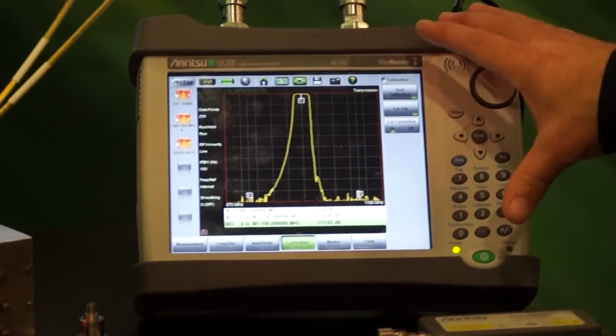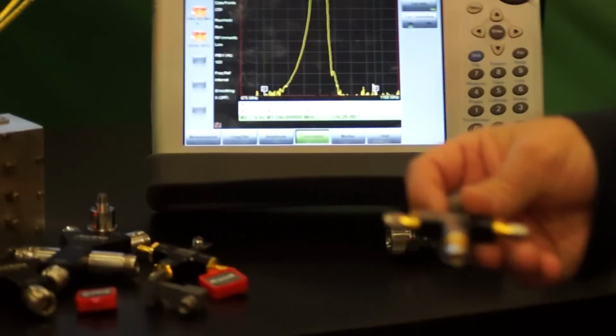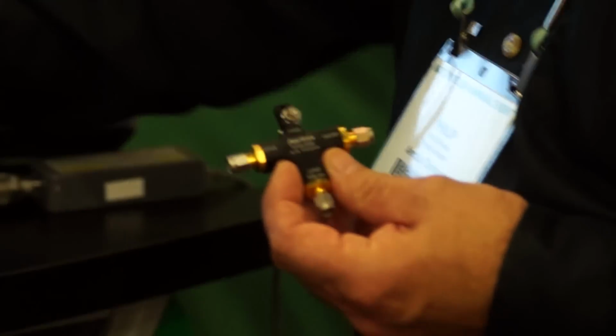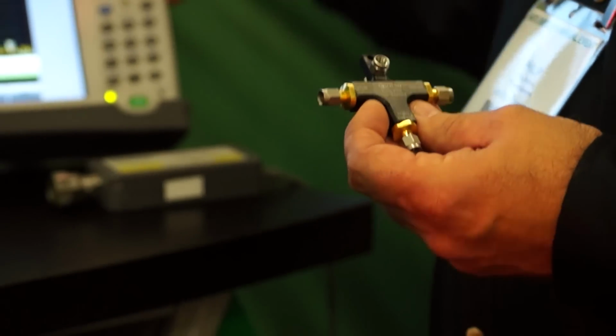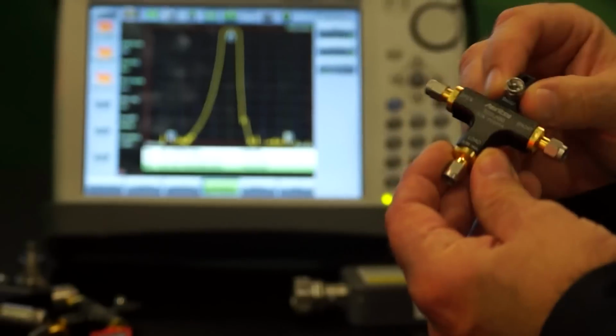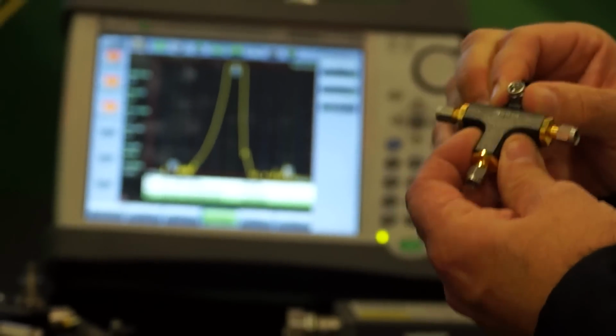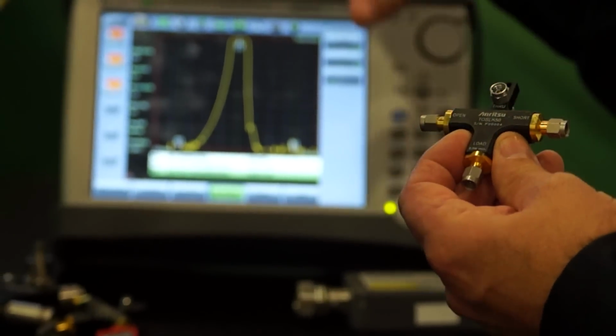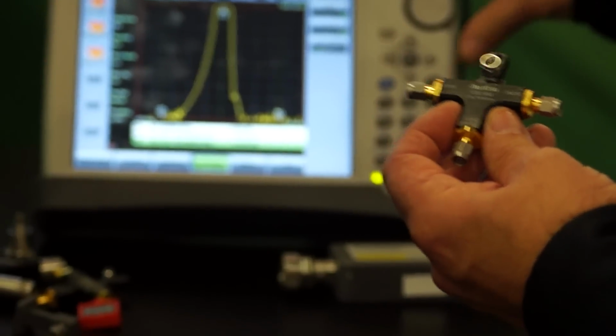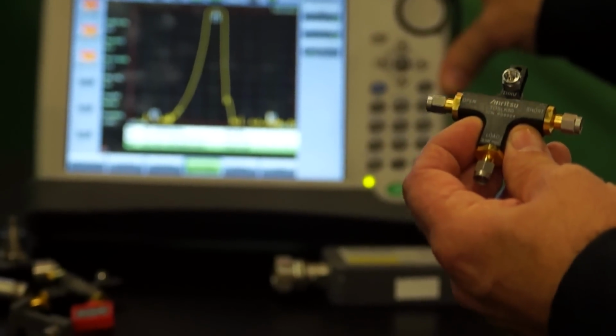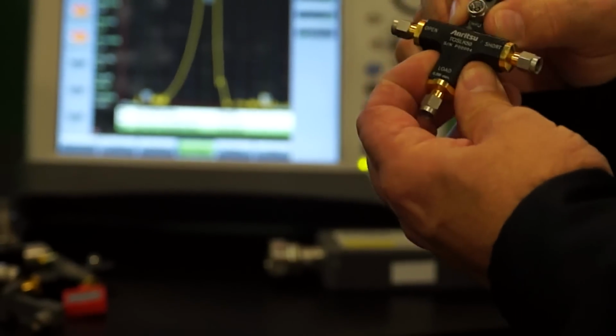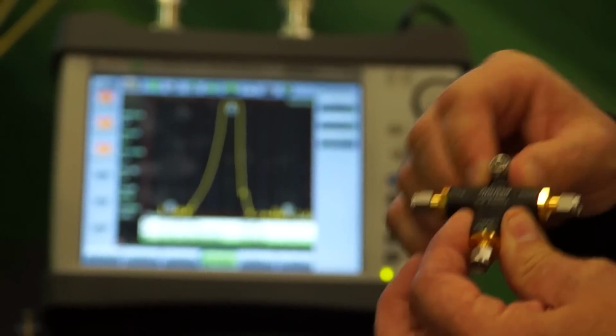Something else I wanted to point out: we've also developed a new series of calibration kits that were designed to go along with this launch, but they will be supported with our other handhelds. These high-performance calibration kits are guaranteed across the full temperature range that the instrument operates, which is -10 to +55 degrees Celsius, which is unique for calibration kits of this nature. They're normally limited to a much smaller temperature range.